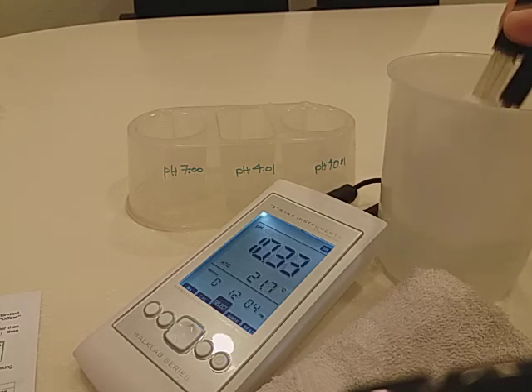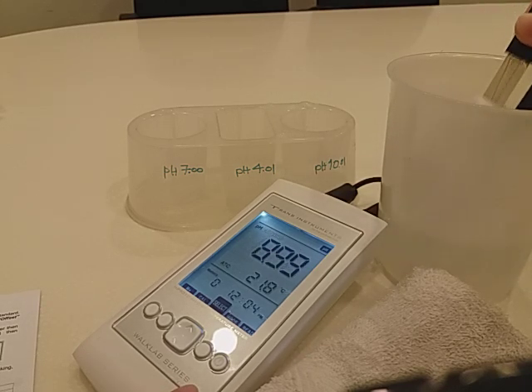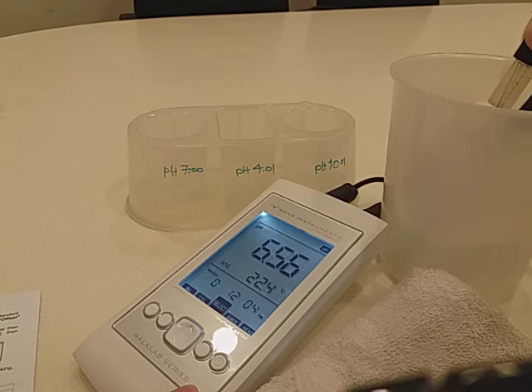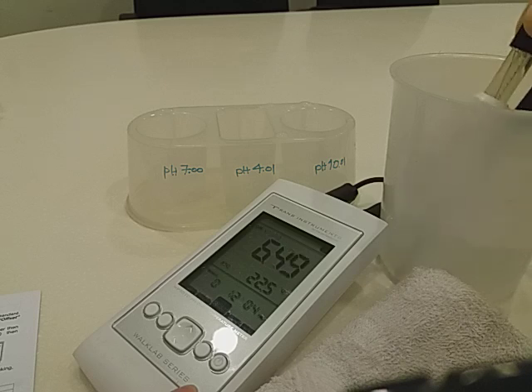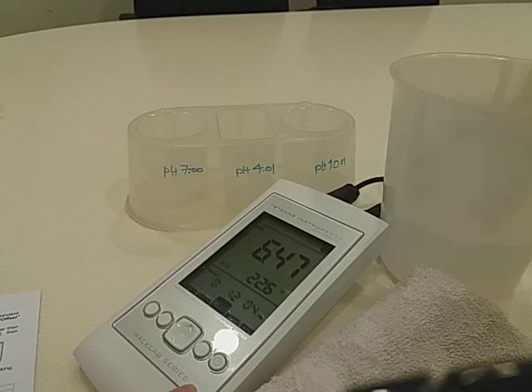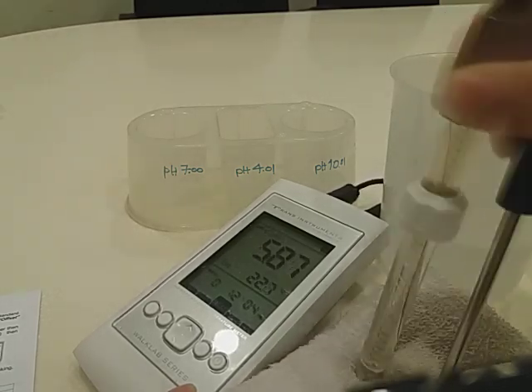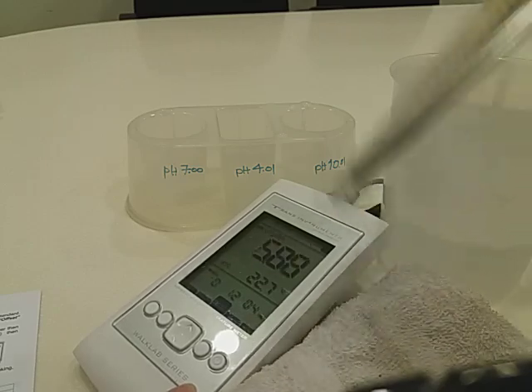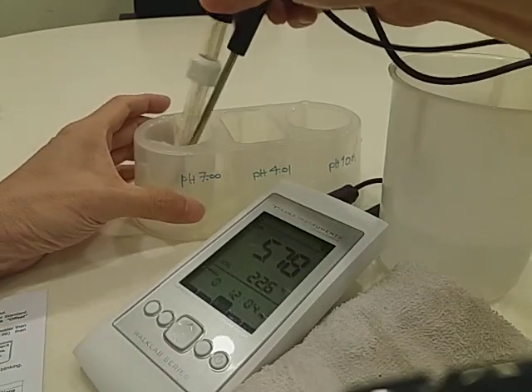Now we go into pH 7 solution just to confirm that we have calibrated correctly. And do remember, the accuracy of this meter is plus and minus 0.01 for the meter, and for the electrode it could be more depending on the accuracy or whether it's a new or old electrode.